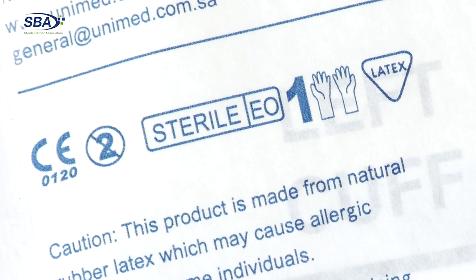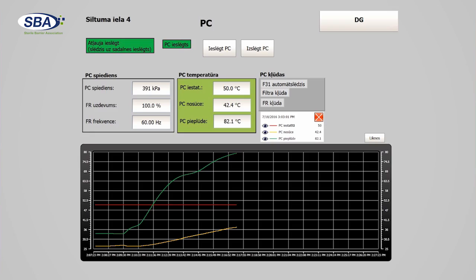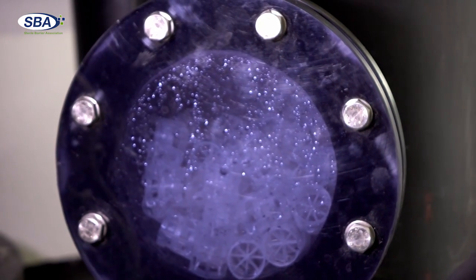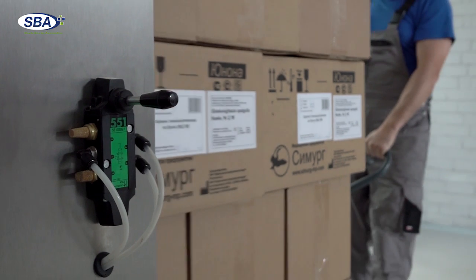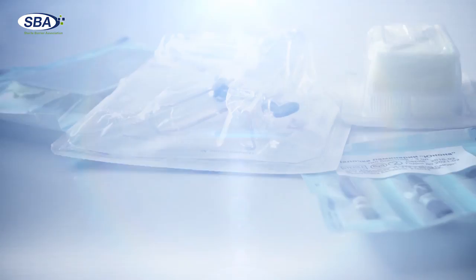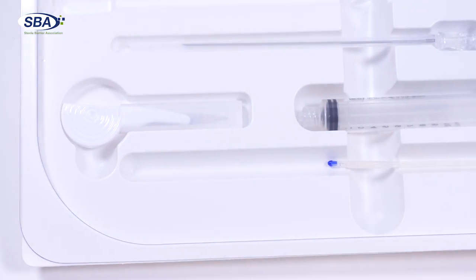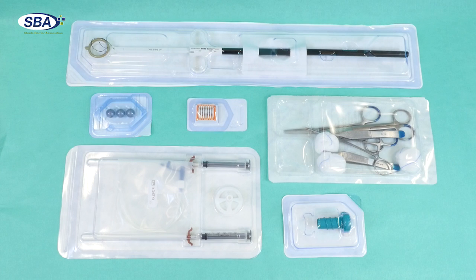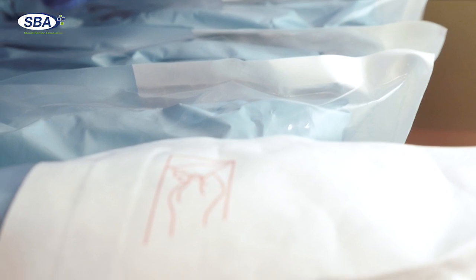Ethylene oxide sterilization uses ethylene oxide gas, which is a chemical agent that kills microorganisms by interfering with normal metabolism of protein and reproductive processes leading to death of cells. Ethylene oxide sterilization is typically carried out between 30 and 60 degrees Celsius, with the relative humidity above 30% and a gas concentration between 200 and 800 milligrams per liter. A complete cycle will take 24 to 36 hours depending on cycle specification. Ethylene oxide sterilization is commonly used to sterilize devices that are sensitive to temperatures greater than 60 degrees Celsius or are moisture sensitive. The sterile barrier system must be porous to allow the sterilizing gas into the pack and be withdrawn after sterilization.